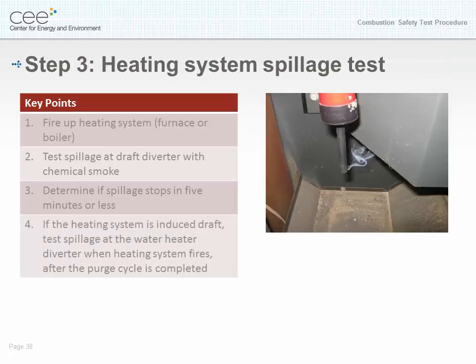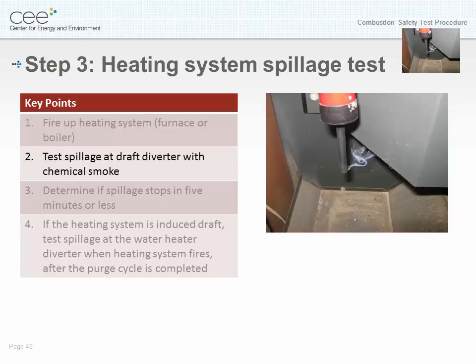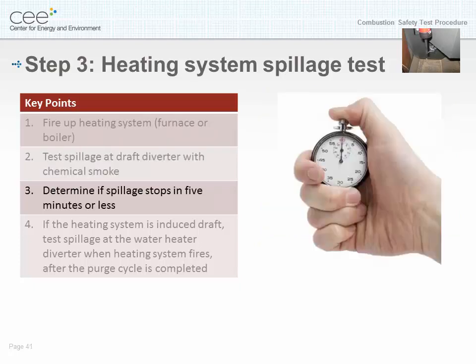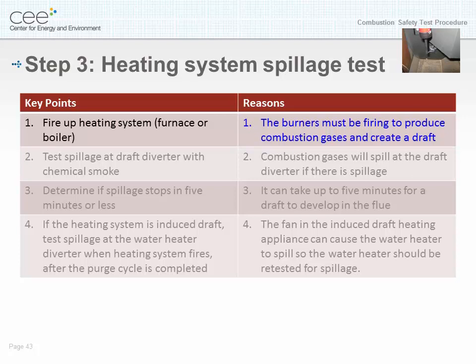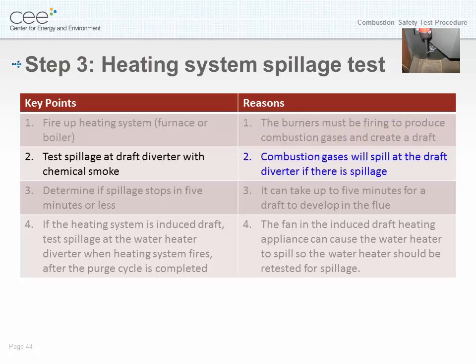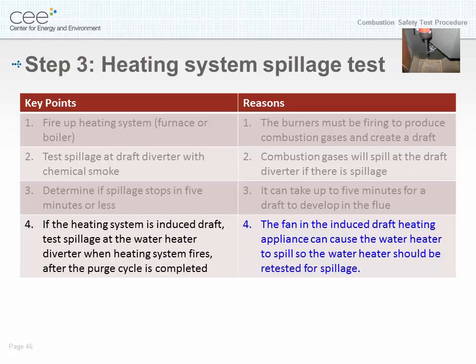Step three: heating system spillage test. Key points: number one, fire up the heating system — the furnace or the boiler; number two, test for spillage at the draft diverter with chemical smoke; number three, determine if spillage stops in five minutes or less; number four, if the heating system is induced draft, test spillage at the water heater diverter when the heating system fires, after the purge cycle is completed. Reasoning: burners must be firing to produce combustion gases and create a draft; combustion gases will spill at the draft diverter if there is spillage; it can take up to five minutes for a draft to develop; and the fan in the induced draft heating appliance can cause the water heater to spill, so the water heater should be retested for spillage.